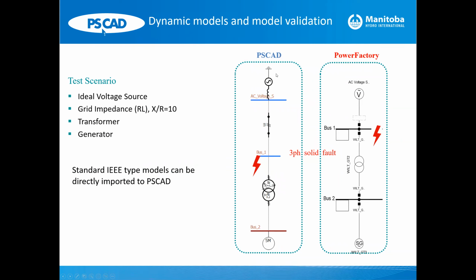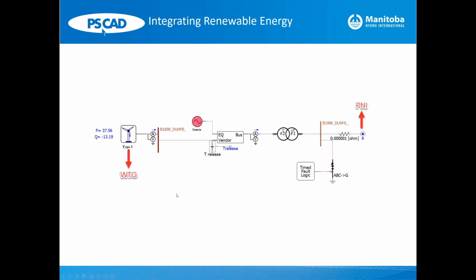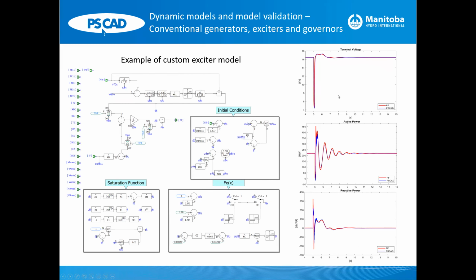So here is a case in Power Factory. If you're going to test your generator model, my recommendation is to first create a single machine infinite bus setup where you take one generator only with all its controls, connect it to a SMIB case, and then use a PSCAD conversion tool to achieve a network equivalent.